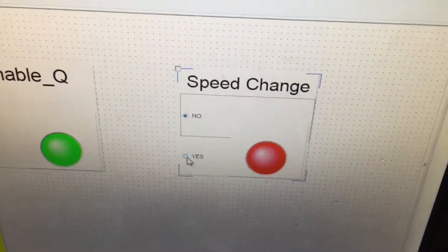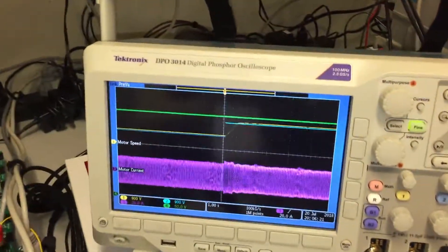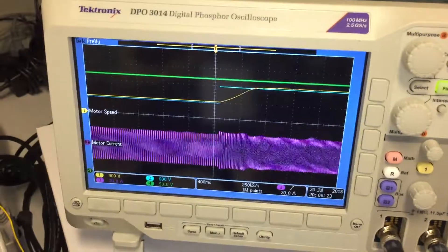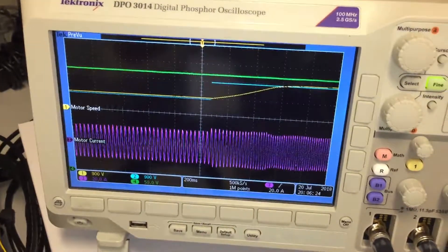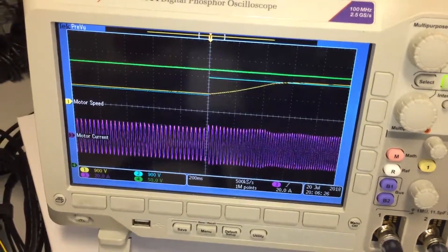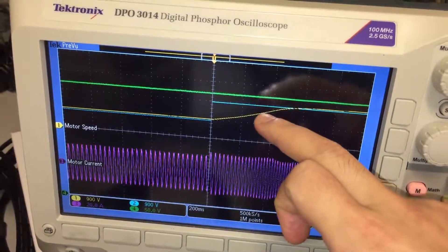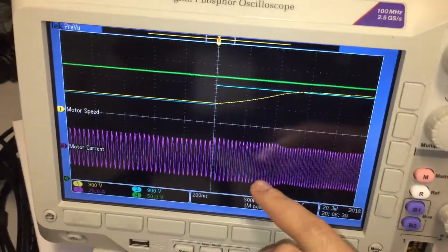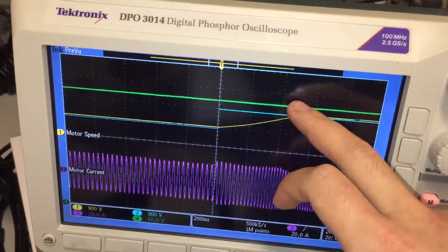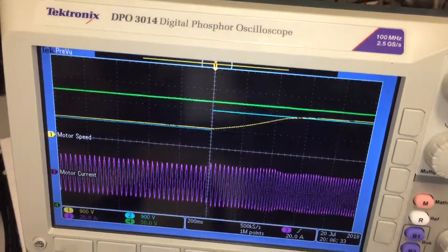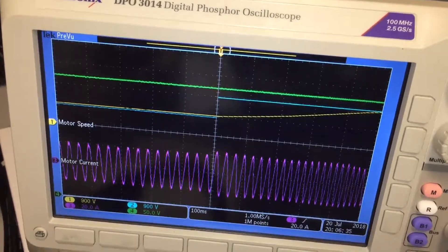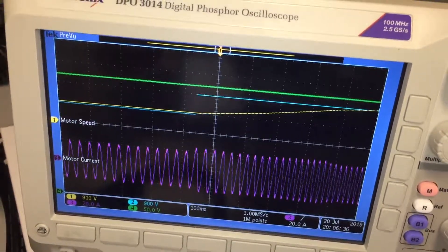I can also increase the motor speed using this button. The motor speed has increased from 900 rpm to 1800 rpm. You can see the speed signal, motor current, and capacitor voltage — it is very stable during this transition.